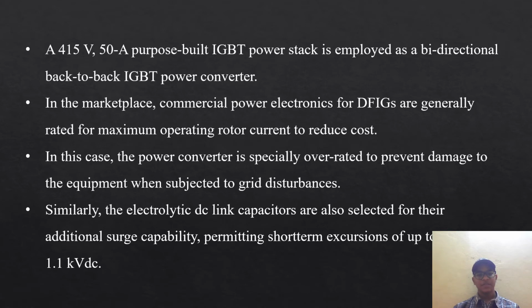IGBT power converters. A 415 volt 50 ampere purpose-built IGBT power stack is employed as a bidirectional back-to-back IGBT power converter. In the marketplace, commercial power electronics for DFIGs are generally rated at the maximum operating rotor current to reduce cost. In this case, the power converter is specially overrated to prevent damage to the equipment when it is subjected to grid disturbances.